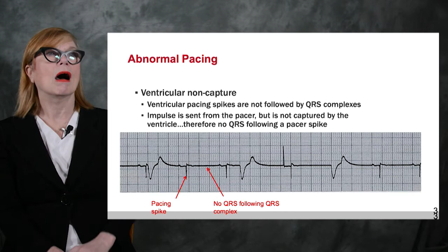So, failure to capture. Insufficient energy delivered by the pacer, turn up the mA. It may be that your battery is low. Look at your pacemaker, you'll get a signal that says battery is low. Now you may have dislodged the wire, it could be loose, there could be fibrotic tissue around it, the electrode could be fractured. There's nothing you can do about that except replace the pacemaker. And electrolyte abnormalities, metabolic acidosis, profound hypoxemia, and hypokalemia.